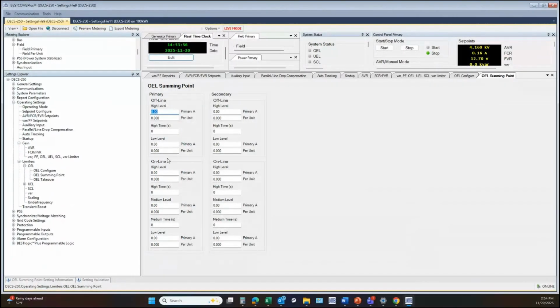Most of the time, there are two options for the overexcitation limiter. You can either choose summing point or takeover style. If you choose a summing point, it'll have a setting screen that looks similar to this. And you want your low level to be above your full load field current threshold. So if your full load field current is 10 amps, you want this set to maybe 0.5% above that. And then you want to increase your other limit levels from there.